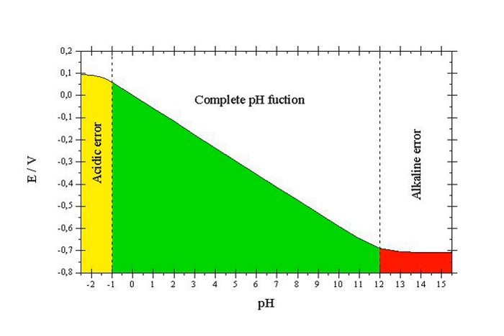Ag/AgCl/KCl, 1 × 10−7 M H+ solution, glass membrane, test solution, junction, KCl/AgCl/Ag. In this schematic representation of the galvanic cell, one will note the symmetry between the left and the right members as seen from the center of the row occupied by the test solution, the solution whose pH must be measured.